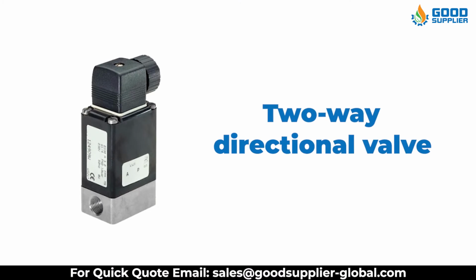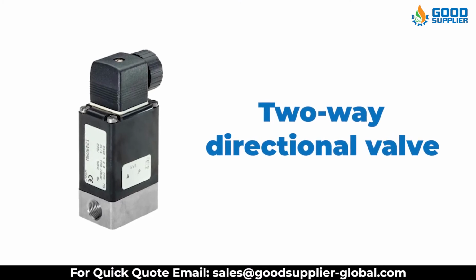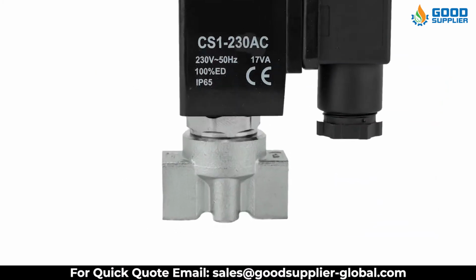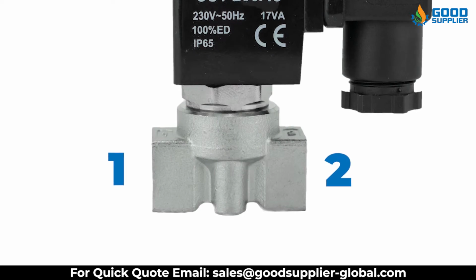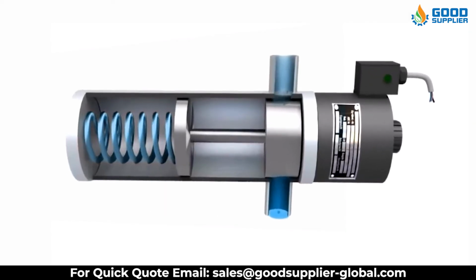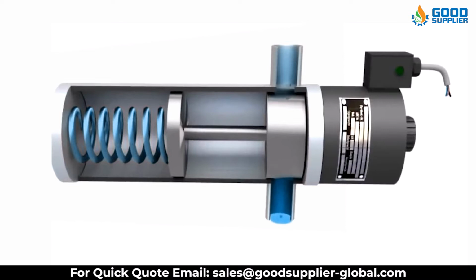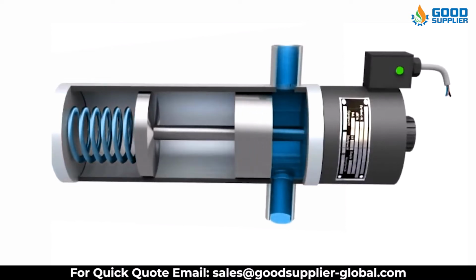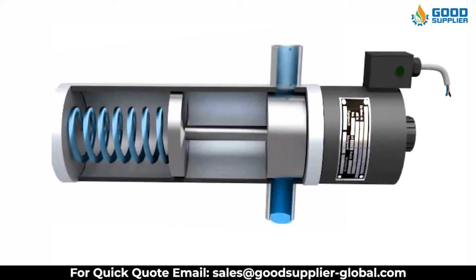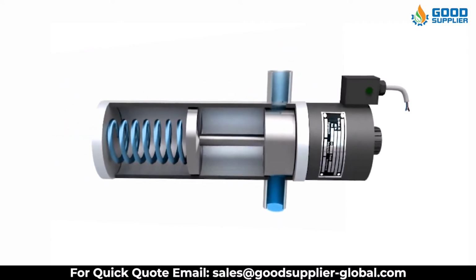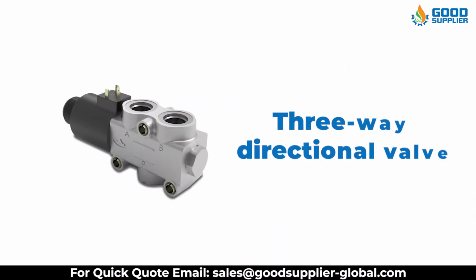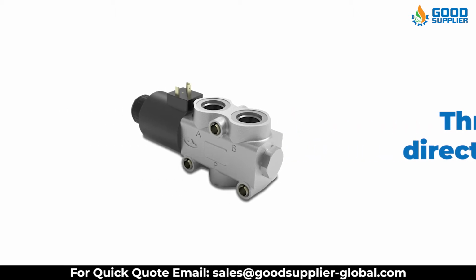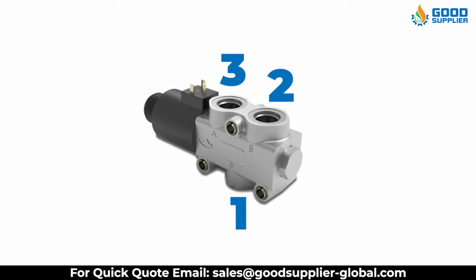A two-way directional valve passes air in 2 directions, through 2 ports, which can be open or closed. If the valve ports are closed, no air can flow through the valve. If the ports are open, air may move from the first port through the valve and the second port or in the opposite direction. A directional 3-way air valve has 3 ports, each of which serves a different purpose.